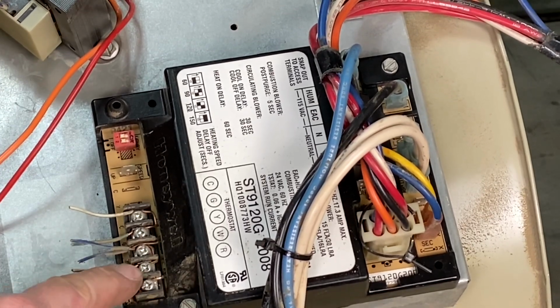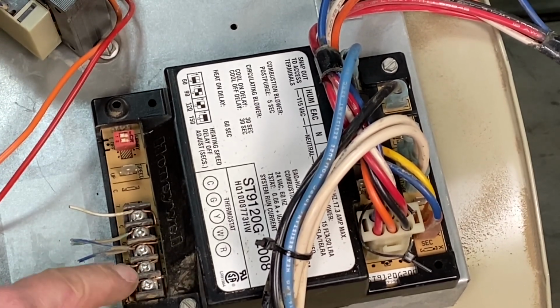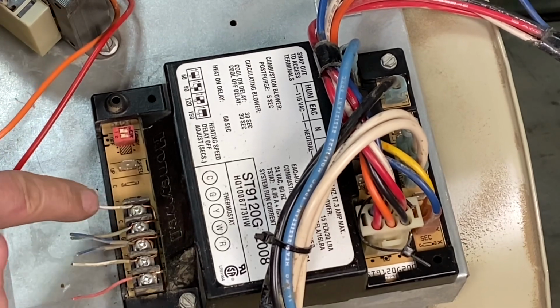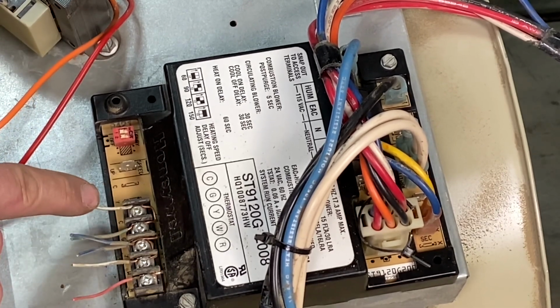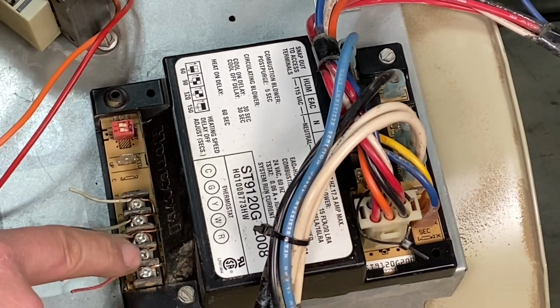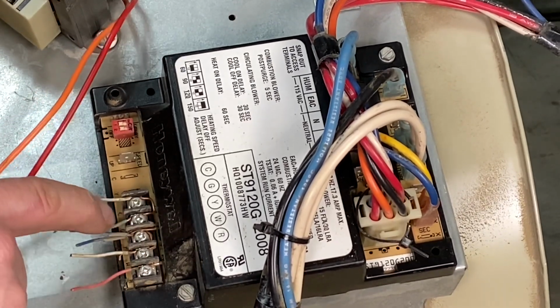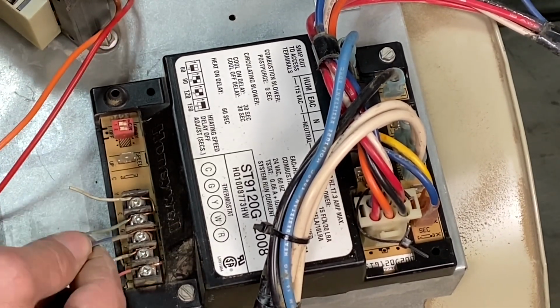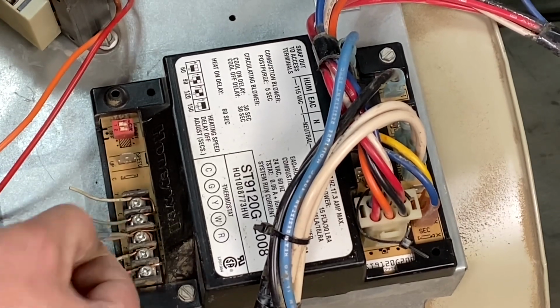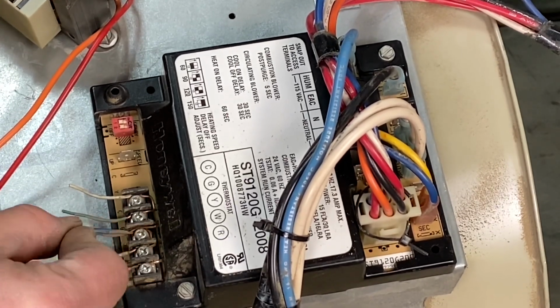Now W stands for heat, it doesn't stand for white. Notice over here, common is also a white wire. So if you just put all the wires together by color, you could actually cause a short by putting those in the wrong location. So very important. Also, they used blue wires for Y. Perfectly fine. So Y is blue, not yellow. Don't get hung up on the colors.